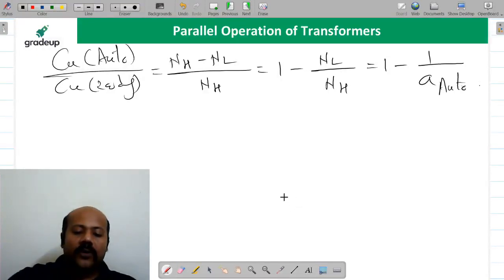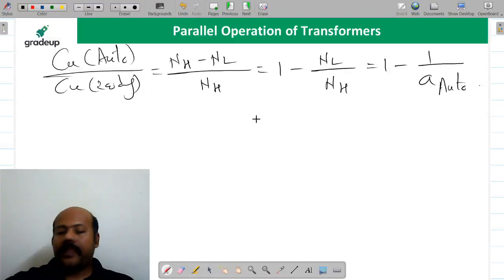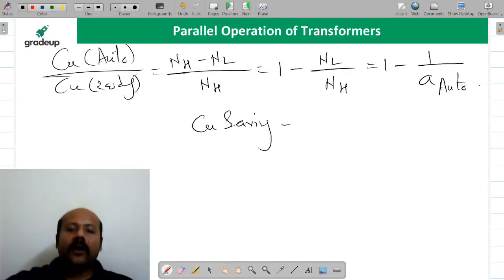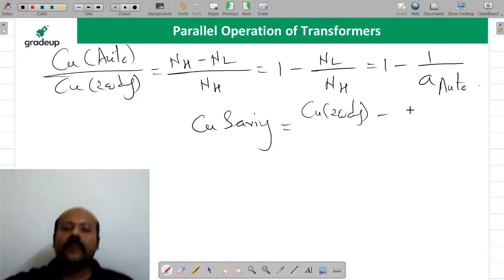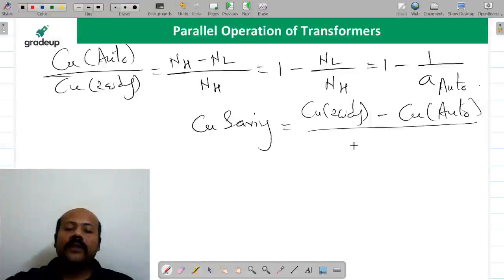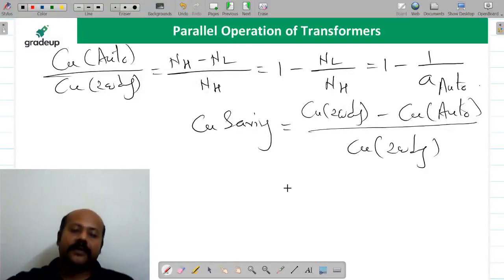Now if you want to know the saving in the copper, if you want to know the copper saving, then copper saving is going to be what? Where are you using more copper? You are using more copper in the two-winding transformer. So it is going to be copper in the two-winding transformer minus copper in the autotransformer, divided by, with respect to what? Copper in the two-winding transformer.